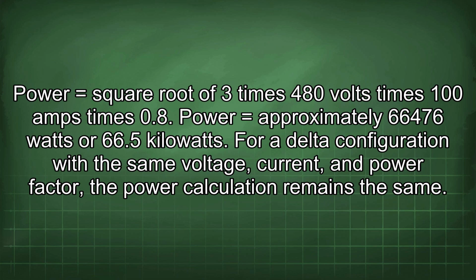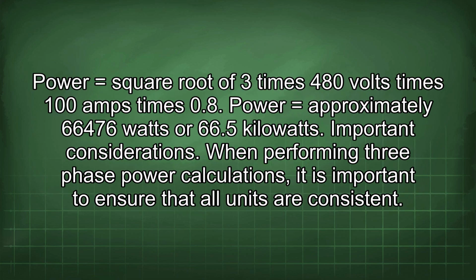For a delta configuration with the same voltage, current, and power factor, the power calculation remains the same. Power equals square root of 3 times 480 volts times 100 amps times 0.8. Power equals approximately 66,476 watts or 66.5 kilowatts.